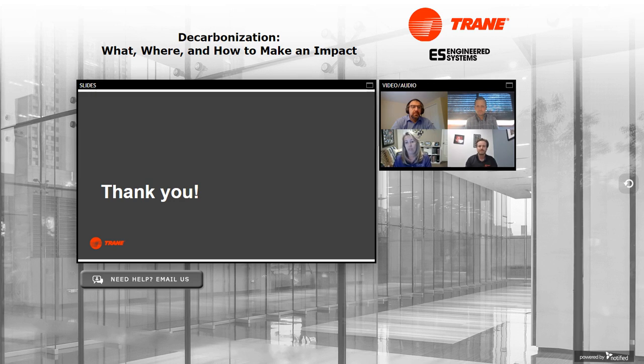Yeah, we also have defrost when we look at our air source heat pumps. Our new Ascend ACX is dual circuit, and so only one circuit goes into defrost at a time. It's programmed such that defrost will have minimal impact on your heating. And from a modular standpoint, we send the modular units into defrost one at a time, so never at any time is your entire system switched to defrost. You always have at least a circuit or a module or two in heating, so the impact is very small.